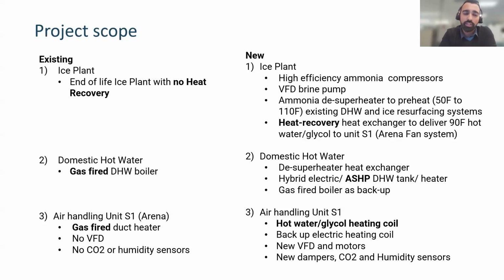So this is on the ice plant side. On the domestic hot water side, as I mentioned, we'll have the desuperheater, which will take the incoming domestic cold water from 50 Fahrenheit to 110 Fahrenheit. And then we have a hybrid electric heat pump, which will supplement and get the temperature to 140 Fahrenheit. We also, in most cases, you will see that we are keeping our existing equipment in place to act as a backup. So the gas-fired boiler that we have today, it's a pretty efficient condensing gas boiler. So that will stay in place.